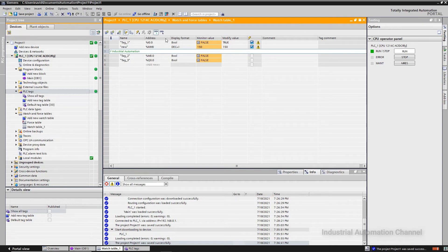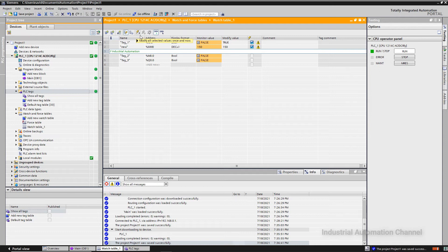But we have modified it — what is the problem? If you look at the modify button, it says 'modify once and now.' This means it modifies your value immediately only once per click. Next CPU cycle, the CPU checks your input and connected push button, sees the push button is not pressed, and therefore changes the input back to logic 0 or off. This process occurs very fast so we can barely see the input in status 1. The integer variable remains 150 because there is nothing to override it — no hardware is connected to it. This is very important, so always remember it.